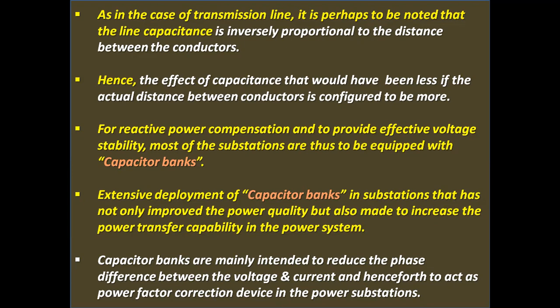For reactive power compensation and to provide effective voltage stability, most of the substations are thus to be equipped with capacitor banks. Extensive deployment of capacitor banks in substations has not only improved the power quality but also increased the power transfer capability in the power system. Capacitor banks are mainly intended to reduce the phase difference between the voltage and current, and hence act as power factor correction devices in the power substations.